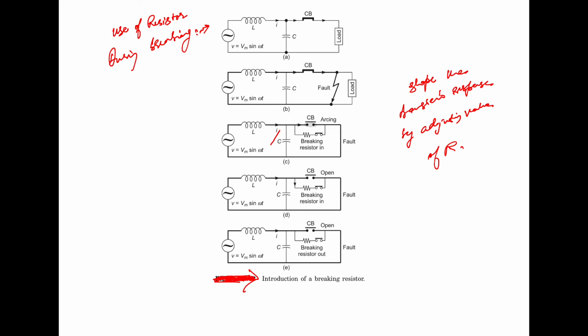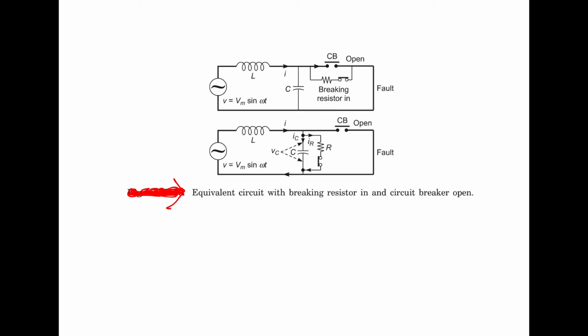So how can the equivalent circuit of the system be modified? Now the equivalent circuit of the system can be modified so that we have the resistors along with that. The figure here shows the equivalent circuit with the breaking resistance, with the main circuit breaker contacts open, but the breaking resistor still within the circuit. So the restriking voltage developed with the resistor in the breaking circuit can be obtained.